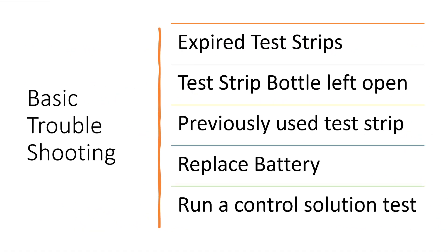Some basic troubleshooting to keep in mind when you are having issues with your blood glucose meter: ensure that you're not using expired test strips, and ensure that the test strip bottle has not been left open, exposing the test strips to an extended period of time to oxygen, which can cause the test strips to not work properly.